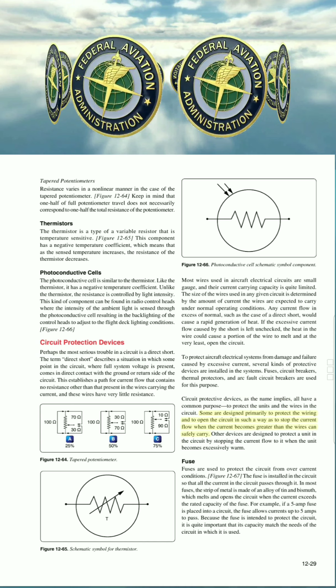To protect aircraft electrical systems from damage and failure caused by excessive current, several kinds of protective devices are installed in the systems. Fuses, circuit breakers, thermal protectors, and arc fault circuit breakers are used for this purpose. Circuit protective devices, as the name implies, all have a common purpose: to protect the units and the wires in the circuit. Some are designed primarily to protect the wiring, and to open the circuit in such a way as to stop the current flow when the current becomes greater than the wires can safely carry. Other devices are designed to protect the unit in the circuit by stopping the current flow to it when the unit becomes excessively warm. Fuses are used to protect the circuit from overcurrent conditions.